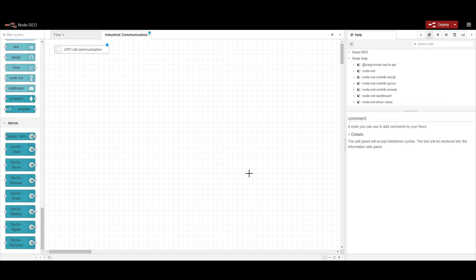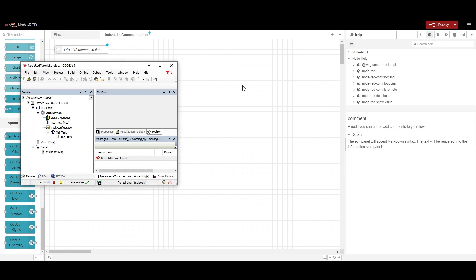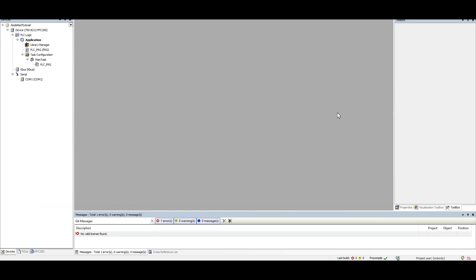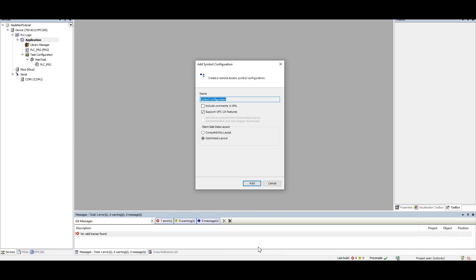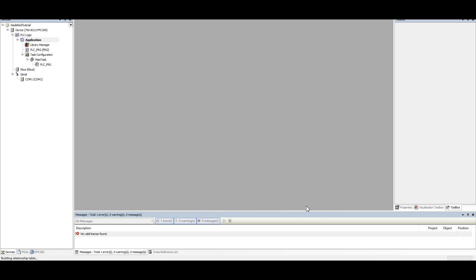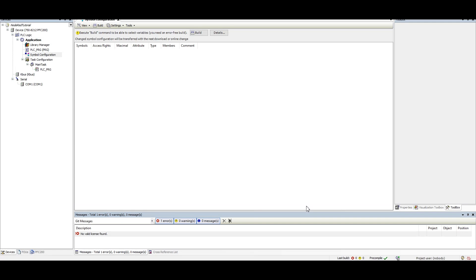Now first we will configure it for the OPC UA client. In order to configure the OPC UA client we need to use the OPC UA client node. Before that I am setting up one OPC UA server — I am utilizing here a WAGO PLC and the Codesys IDE. In Codesys we need to configure the symbol configuration and add some variables so that when we download the code into the PLC it will enable the OPC UA server.